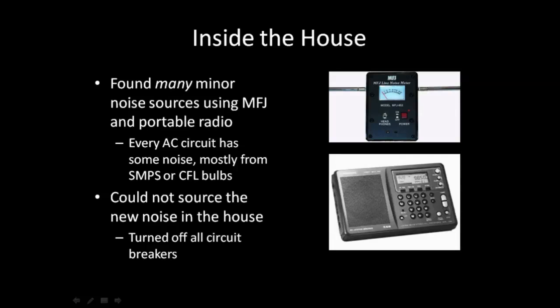Secondly, I went through the house, and this can be a big job, because your house is just full of many minor noise sources, and occasionally major ones too. You can use the line analyzer or a portable radio tuned to various frequencies. Every AC circuit in your house pretty well has its own noise signature, and most of the noise comes from switch mode power supplies or compact fluorescent bulbs. You can actually just trace along your power lines and know what the various noise signatures are inside your house from different equipment. Of course, if you found something bad, you can just unplug it. The gold standard for figuring out if something is in your house or not is to turn off all the circuit breakers, which I did, and that did no good at all because the noise wasn't coming from inside my house.